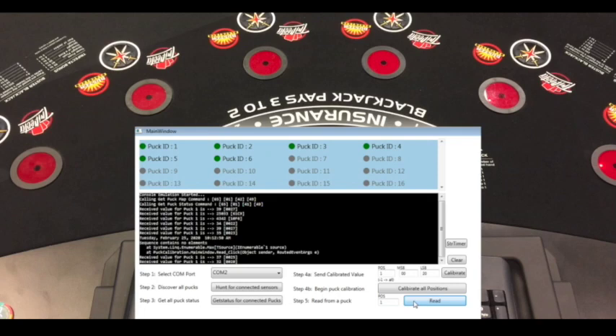That's somewhat normal. If you see that happening a lot, so if you're reading just one sensor and you're getting a whole bunch of these "sequence contains no elements," it could be that that sensor is bad. We need to move that sensor to another spot and see if it follows or see if there's something wrong with that hub. So let's say spot number 3 gave us the issue and we kept getting "sequence contains no elements." We move that sensor to number 1 and it doesn't follow, but we test 3 and it's still doing it, that's a bad hub. But if it follows, then it's a bad sensor.